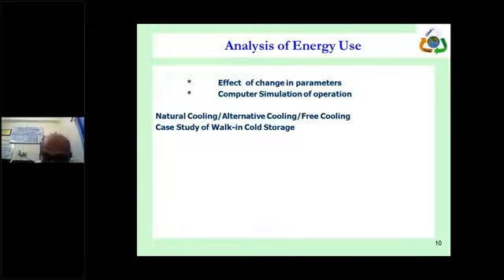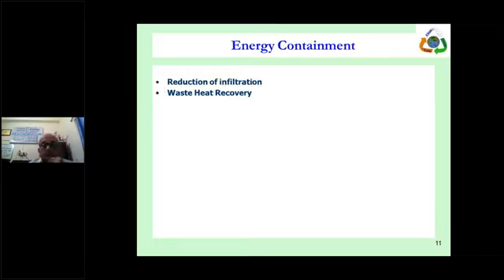So this way we can also cross check the real need, and it may even harm the purpose, in fact. So you are serving a double purpose: you are saving energy as well as avoiding potential losses. The next idea we can apply in the air conditioning energy principle is energy containment. Containment means not allowing heat or cooling to go out.